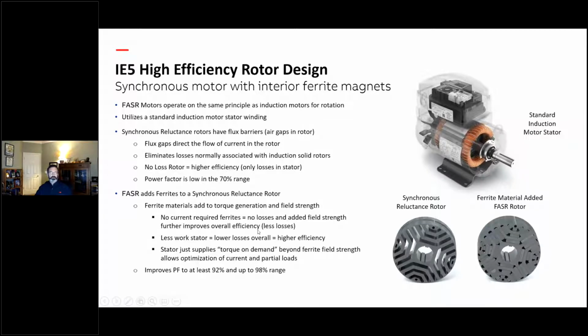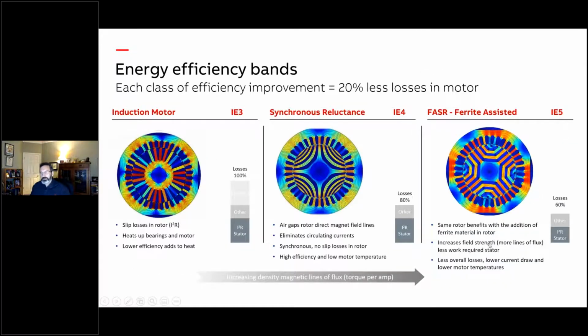But we already talked about the low power factor. So the FASR motor with the ferrites adds magnet material here into those air gaps, boosts your power factor up. It drops your current draw of the motor, and it does a lot of the work of the stator. So it basically does about 30% of the work of the stator winding. And so that's what reduces the losses in the stator and boosts efficiency. But remember, the whole point here isn't just to boost efficiency, it's to get you better partial load efficiency. The no load current of an induction motor can be as high as 35%, which means it's drawing 35% current no matter what the load is. So if you're at 25% load, you're drawing 35% current, and you're getting 35% of the current losses in the stator winding. Since the magnets do about 30% of the work, if I'm at 30% load, the stator isn't doing anything, which means there's no losses in the stator, which is why you can maintain a really flat efficiency profile.